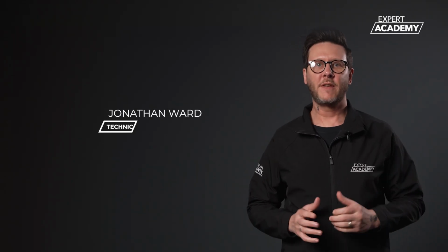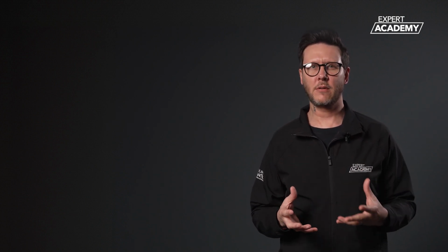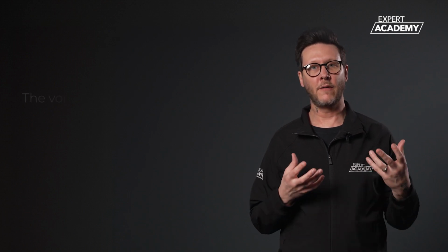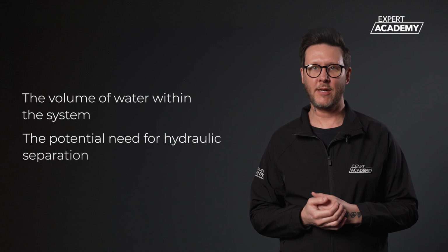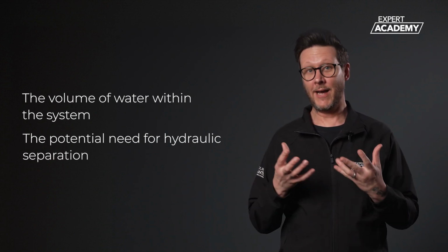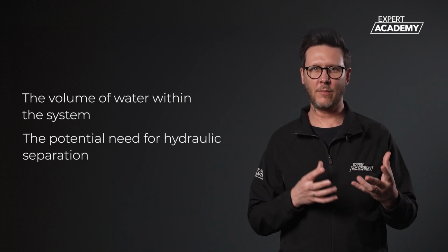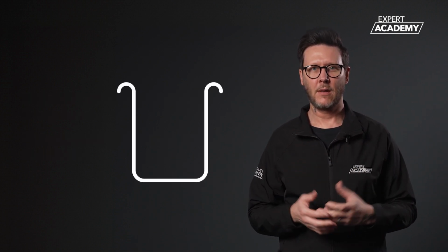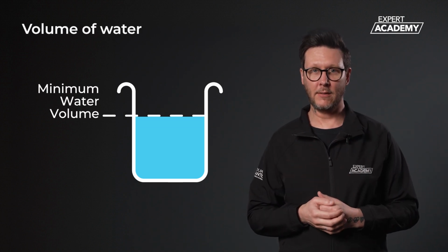To achieve optimal efficiency and reduce running costs when fitting a heat pump, it's essential to ensure that the system is correctly designed and installed. Two key components of a system design are the volume of water within the system and the potential need for hydraulic separation. While other considerations such as pipe sizing and more are important, this section specifically addresses volume and hydraulic separation. Heat pump manufacturers will specify the minimum free water volume required.